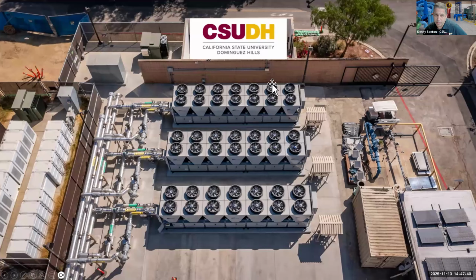And when I say heat pumps, I mean big heat pumps. We got rid of 95% of our gas for heating the campus. The campus central plant feeds about 1.5 million square feet for heating and cooling. We didn't get rid of the condensing boilers. We kept them for backup, so that if it gets really cold, we can turn them on in a pinch.